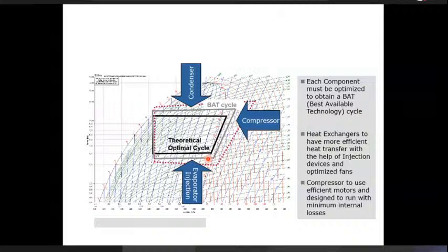Depending on the type of technology that we are using. If we use a reciprocating compressor or a scroll compressor, then refrigerant comes in from the evaporator and passes over the motor before it goes in for compression. That has two major impacts. One is that the compressor motor gets cooled. The second is that any fine droplets in the refrigerant will evaporate because of the compressor heat, and then we can be sure that the compression process will have no liquid particles in it.